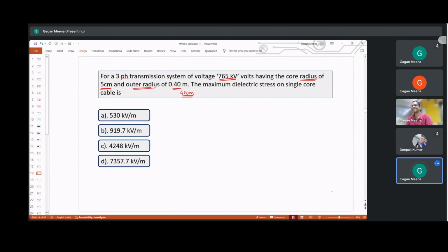For 765 kV, this much will be the width of the cable. This is radius, so diameter would be 80 centimeters, almost 1 meter. That is very huge, so it will be quite a huge cable. As voltage increases, the thickness of the cable also increases. That is why insulation becomes a problem. Providing insulation at 765 kV, especially for underground cables, is very difficult to design, and it will add too much to the cost also.